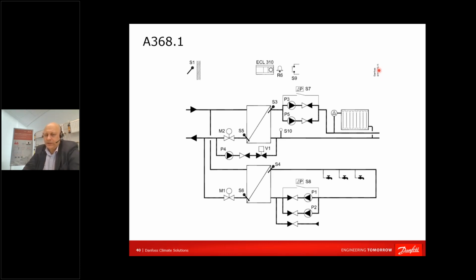That might be one of the scenarios. Yes, you can rely on the smart pump technologies, and yes, that can run okay. The drawback, I do see, is that double pumps normally have an issue: you cannot service them separately. If the pump has a double pump body and you would like to open and clean or fix one of the engines, then you will have to stop heating at that very moment. If I'm mistaken, I can be corrected, but in the scenario where you have two separate pumps, you can disconnect one of the pumps and service or replace it. So there might be a few scenarios.